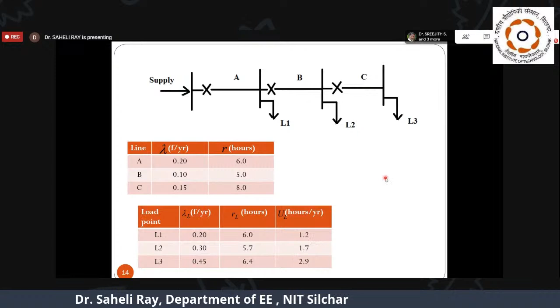So with this knowledge, along with this data, I have taken this table from the previous one, whatever we have derived. If we are provided with the number of customers connected to each of these load points, like L1, L2, L3, and the average load demand, let it be here 1000 kilowatt for load point 1, 700 kilowatt for load point 2, and 400 for load point 3. We have just taken a basic example. We followed the book of Power System Reliability by Roy Billinton. We've taken the example from there.